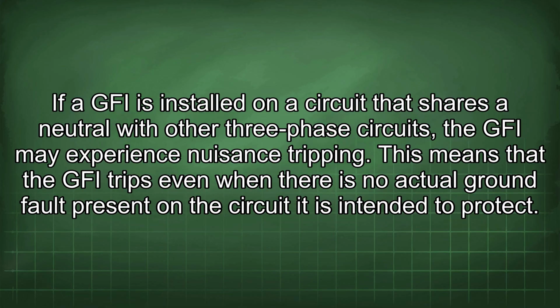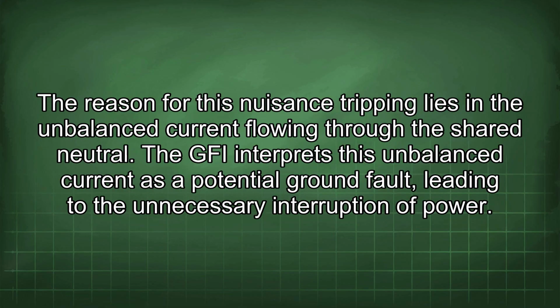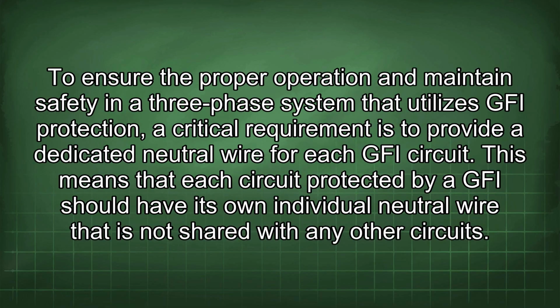This means that the GFI trips even when there is no actual ground fault present on the circuit it is intended to protect. The reason for this nuisance tripping lies in the unbalanced current flowing through the shared neutral. The GFI interprets this unbalanced current as a potential ground fault, leading to the unnecessary interruption of power. To ensure the proper operation and maintain safety in a three-phase system that utilizes GFI protection, a critical requirement is to provide a dedicated neutral wire for each GFI circuit.